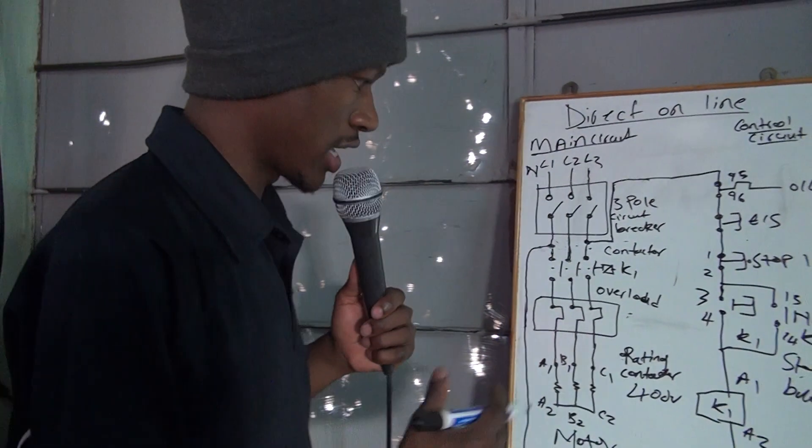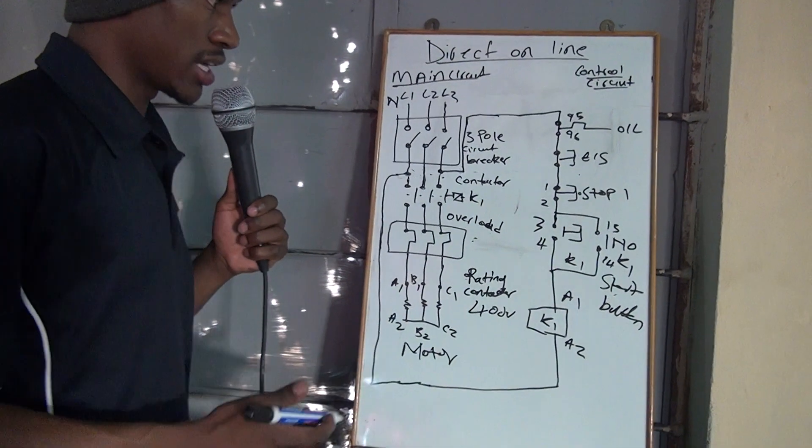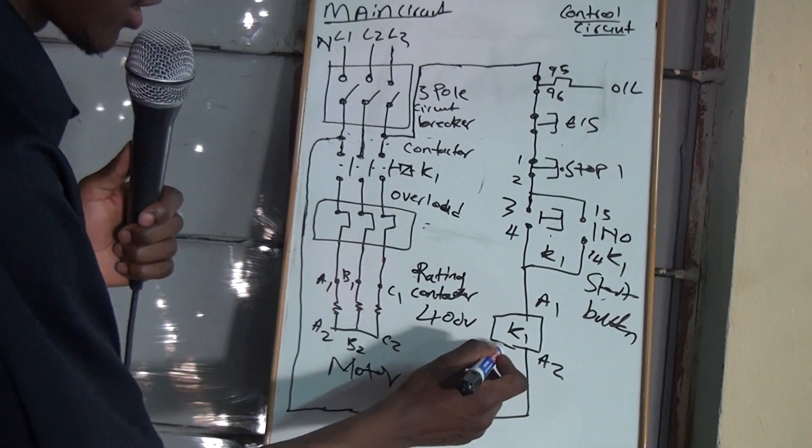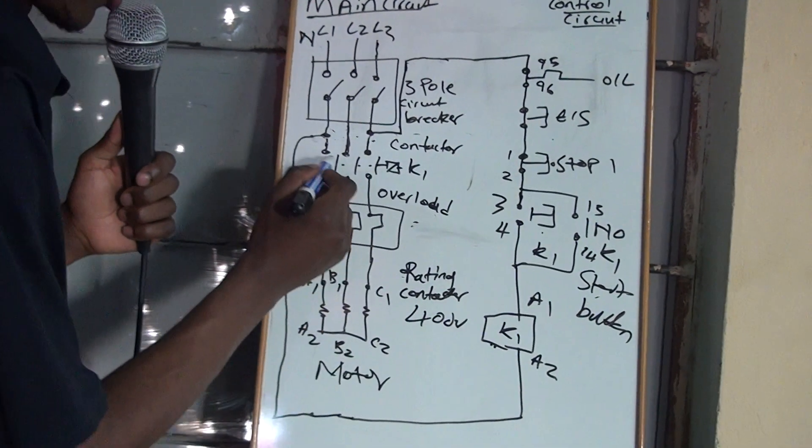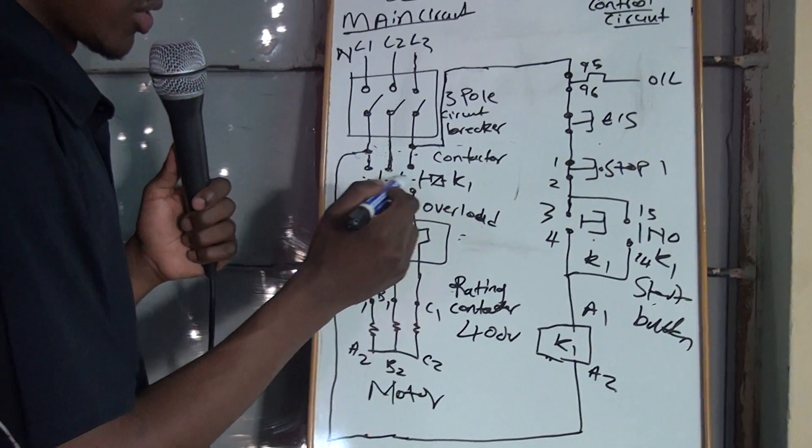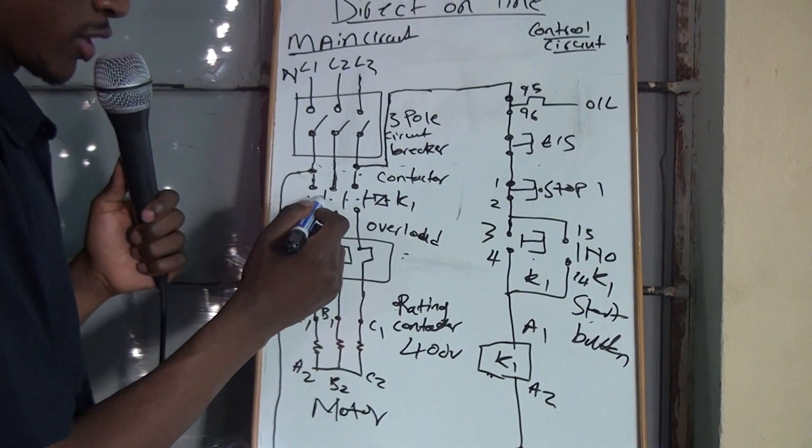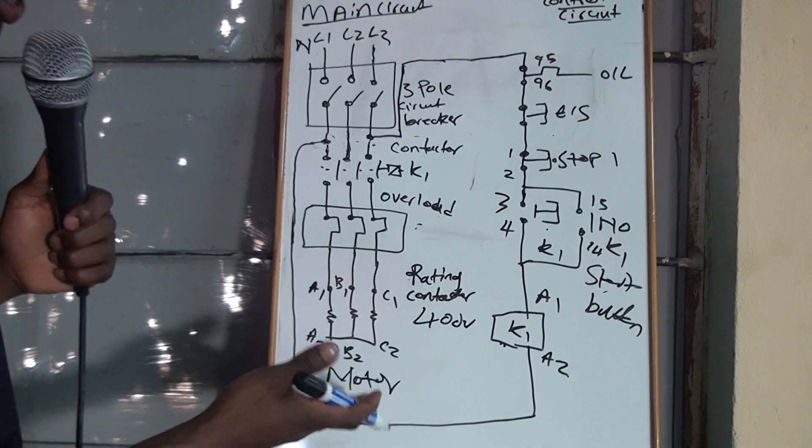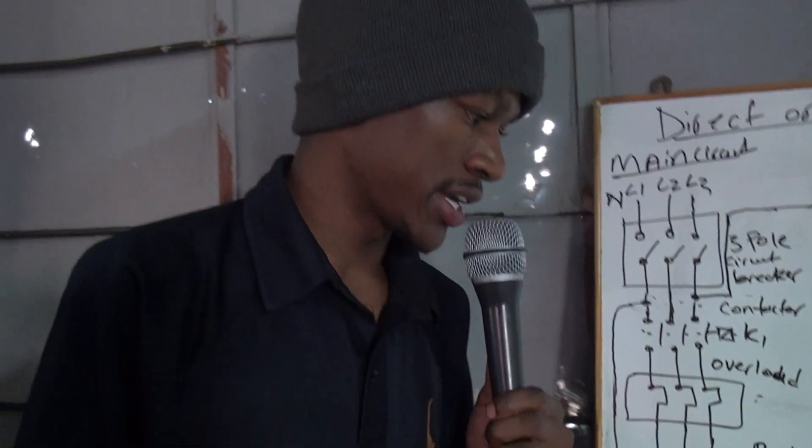That's how you draw your direct on line. And it works in such a way that when you press your start button, the coil energizes. And when the coil energizes, the contacts close. Instead of becoming normally open, now they become normally closed. Then your motor now can run.